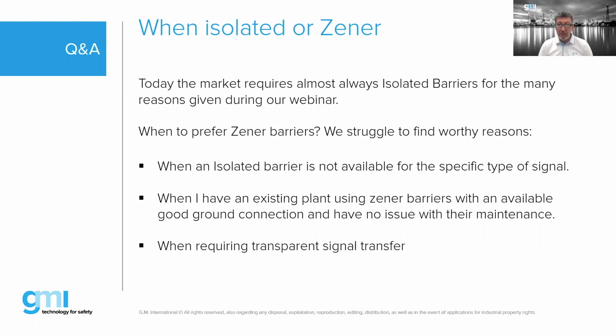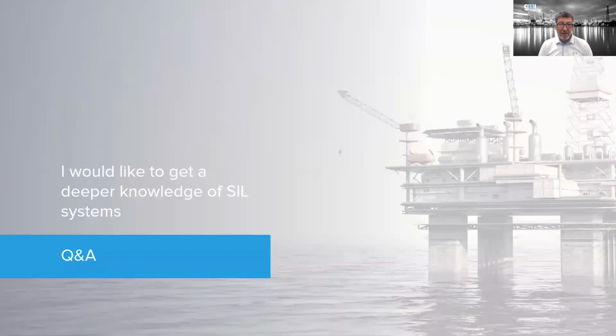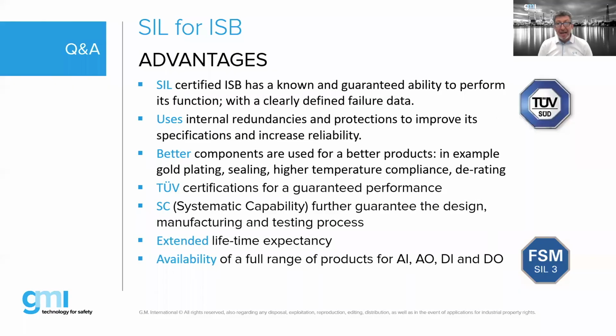I think we're running late here. There was a question about SIL. I want to get more information about SIL. I translated it into something like this. We have webinars on SIL, we have a webinar on functional safety, you can look it up. But, Bob, I believe a barrier being a safety device, somehow a SIL, it's not a requirement for a barrier, right, to have a SIL certification? No. But it's not a bad idea.